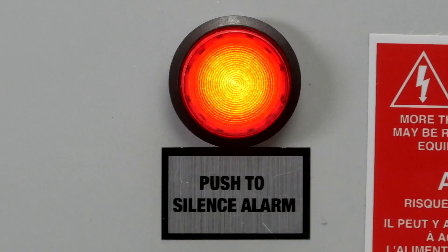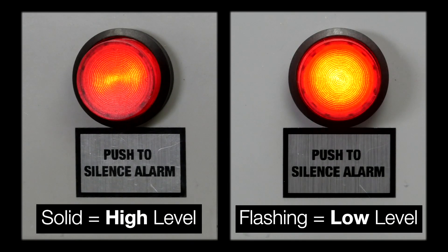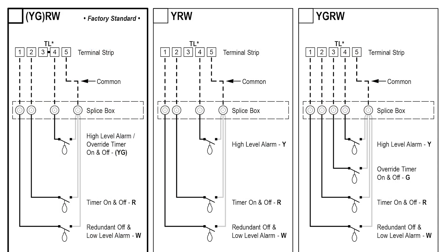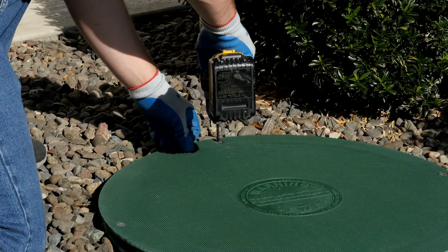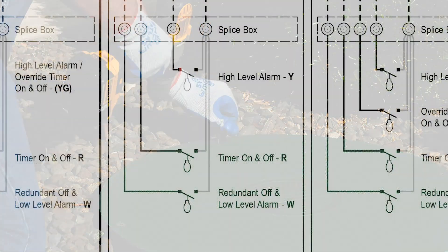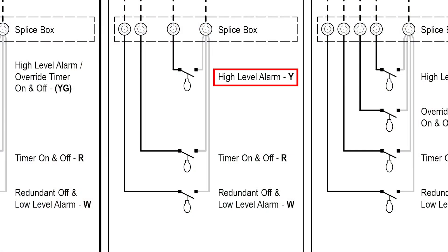If the alarm does occur, the push-to-silence button on the face of the panel will illuminate. For all MVP panels, the light will flash for a low level alarm and remain solid for a high level alarm. For all electromechanical panels with the RO feature, there is no visual indicator to differentiate between the two alarms. You will need to remove the riser lid and visually inspect the level in the tank to determine if the alarm is a high level or low level alarm.